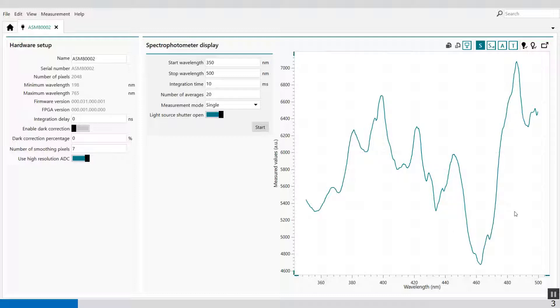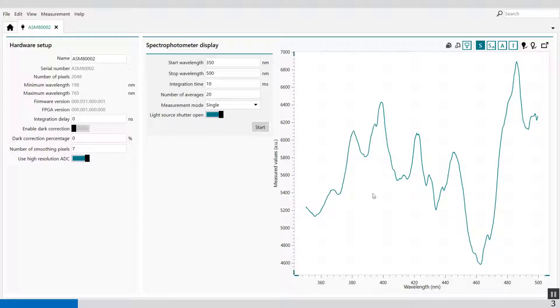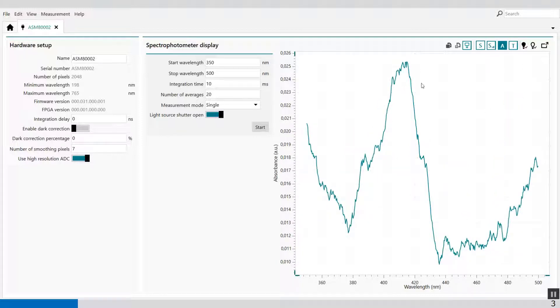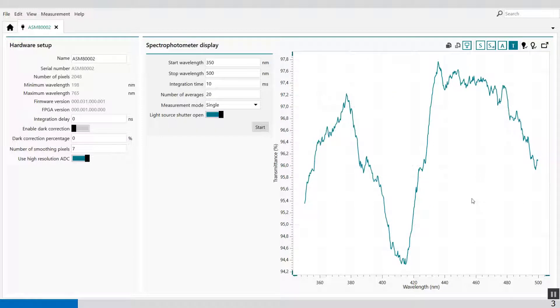What I can do now is put another solution — for example copper sulfate, which is blue — into the cuvette. When I've closed it, I can take another spectrum for the copper sulfate. You'll see the spectrum of copper sulfate. You also see the icons for the dark corrected spectrum, the scope mode, absorbance, and transmittance. We can follow in real time what the absorbance is. You see the absorbance of this copper sulfate peak between 380 and 440 nanometers. The transmittance mode is the inverse of the absorbance, of course.